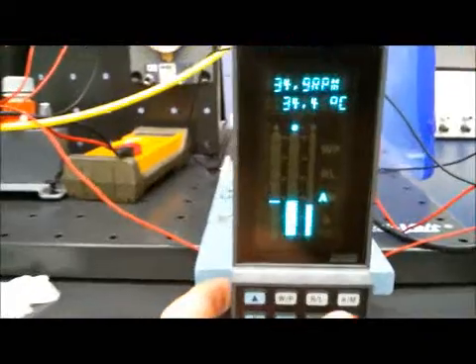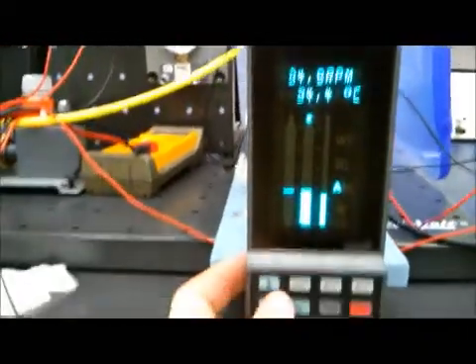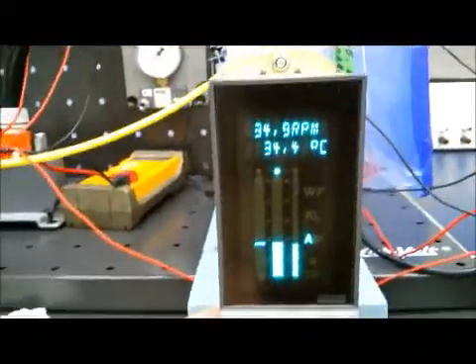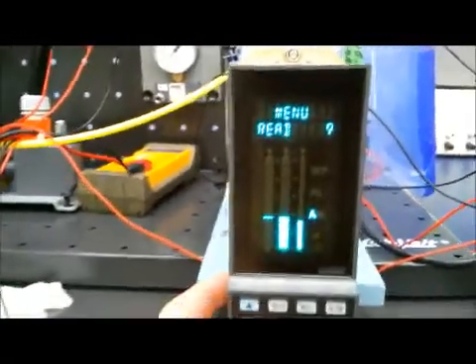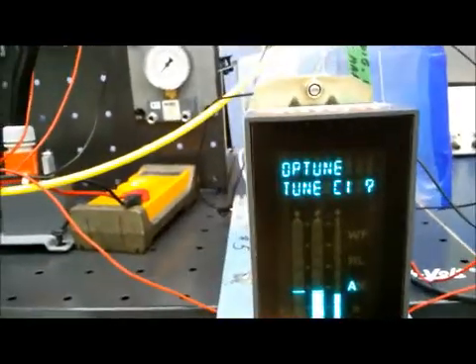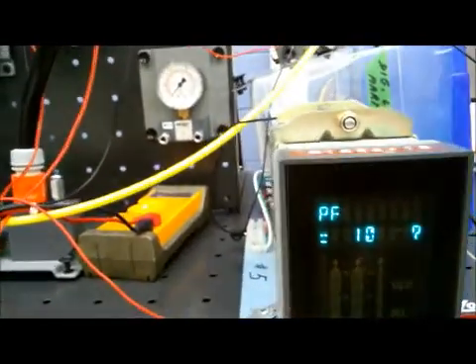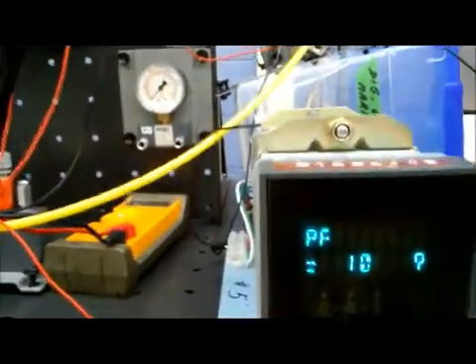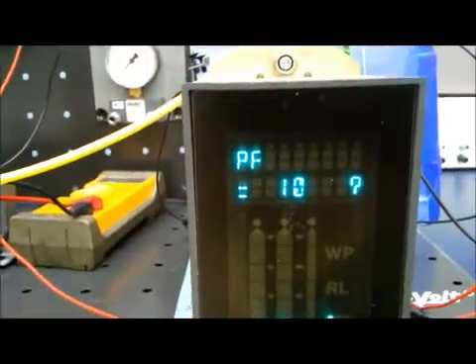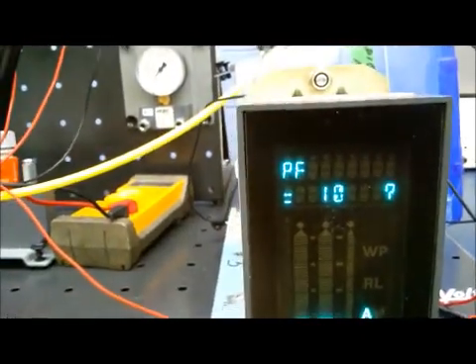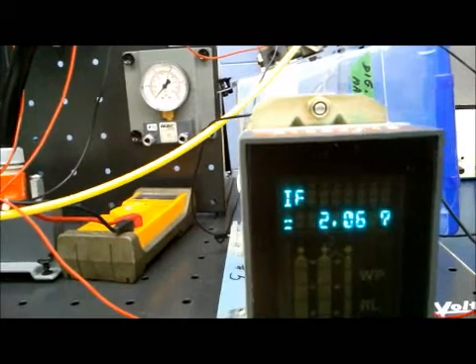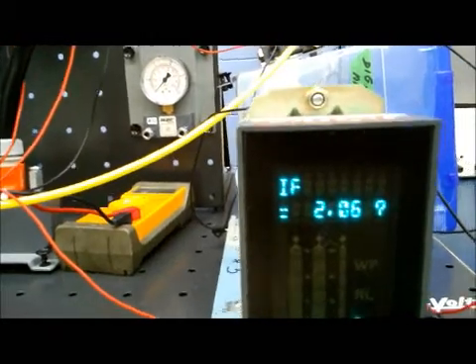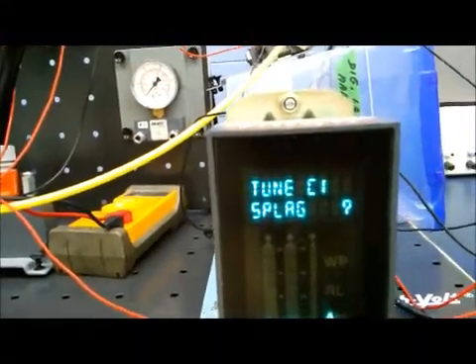My master, you can see the values are, tag, OPTUNE, tune controller one, proportional value or factor is 10%, quite significant. Integral is two minutes per repeat and no differential.